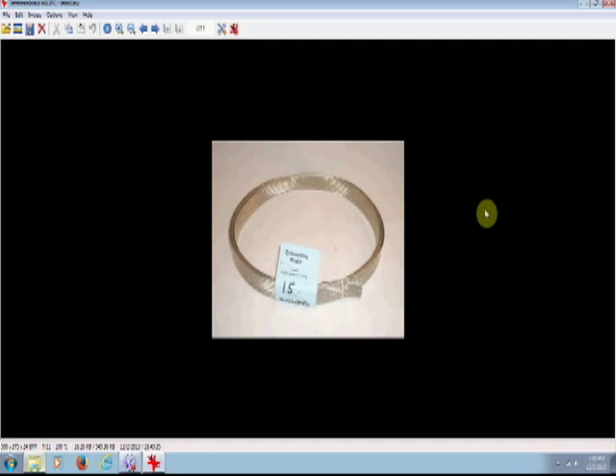I went out to eBay and bought about 25 feet of braid in three-quarter inch. And that's what I'm using to ground all the equipment. So this is what I'm talking about right here, this braid. And of course you can buy it in strips. This is what I did, I bought strips of it off of eBay. And you can buy all different lengths. You know, you want to get at least half inch, preferably three-quarter inch. The one inch is also very good but it gets a little bit expensive. I'd say three-quarter inch will be just fine if you follow all these different techniques. Your ground will be just fine.